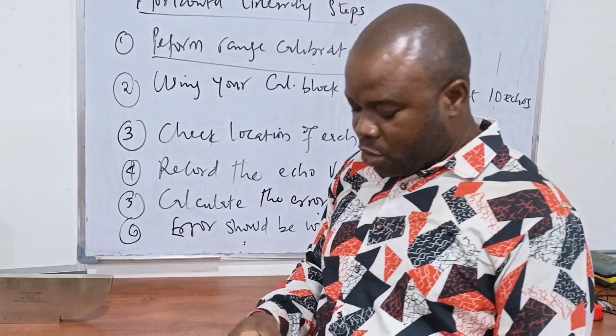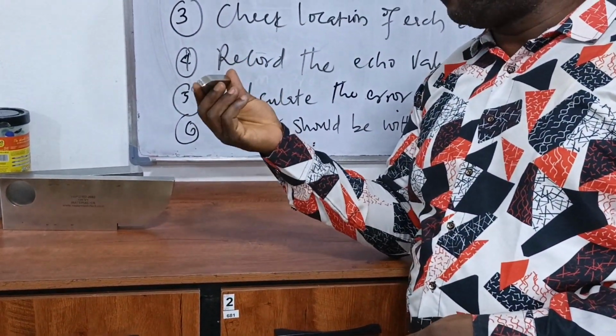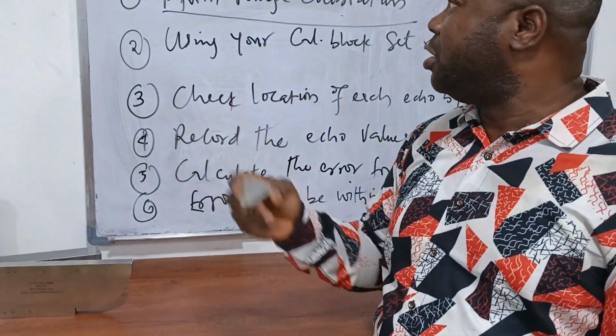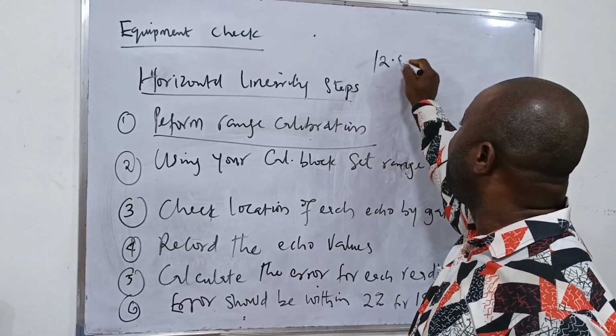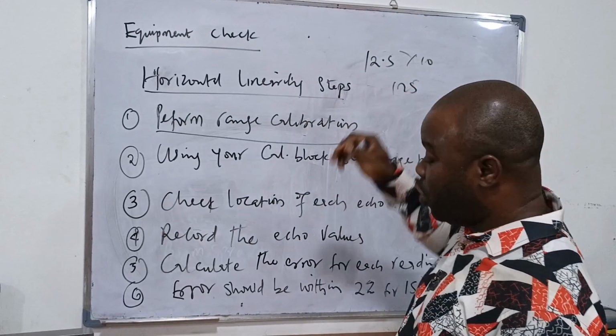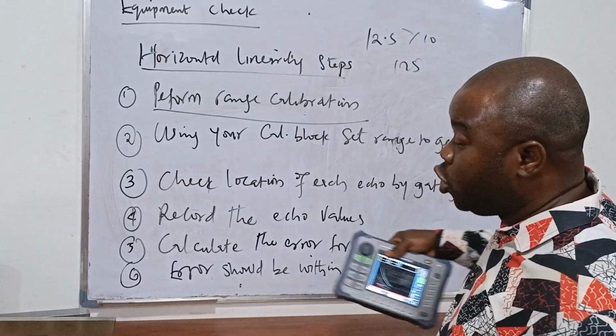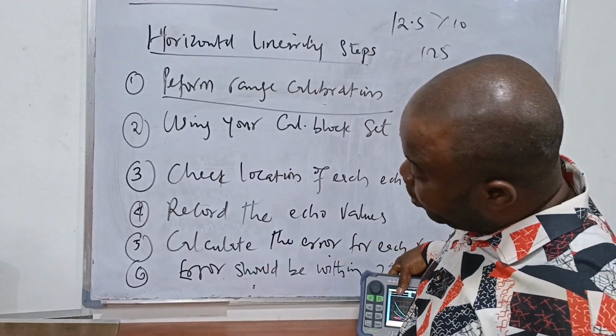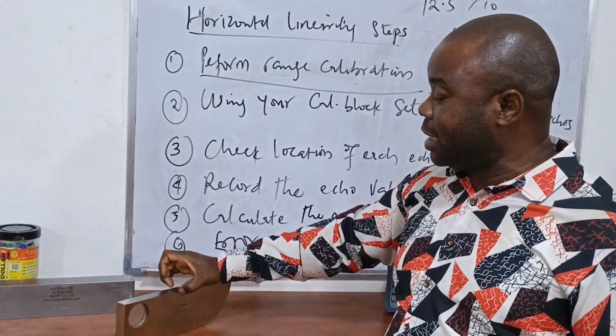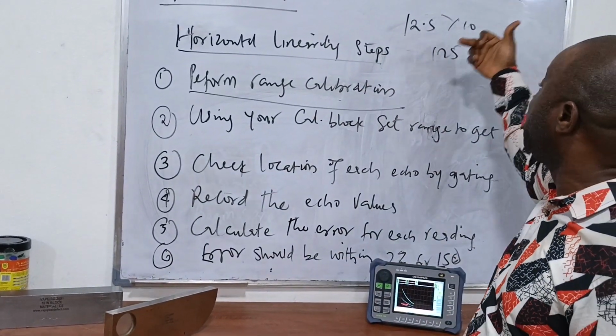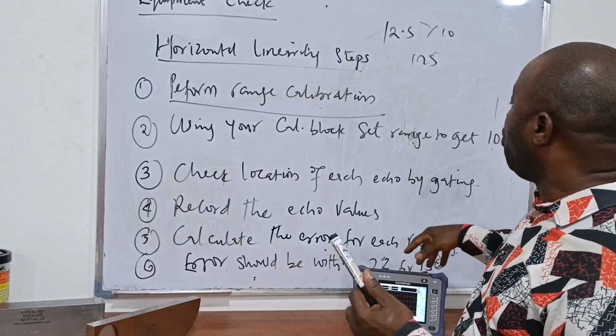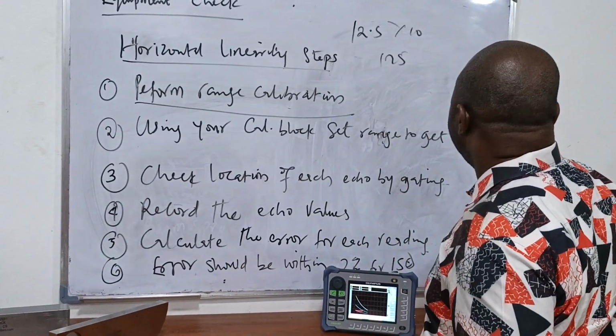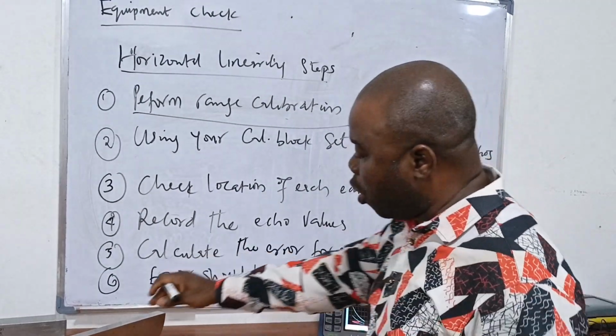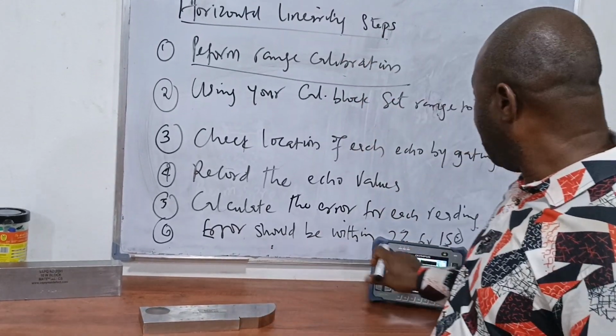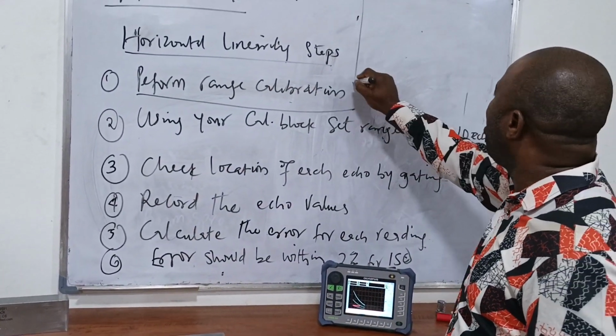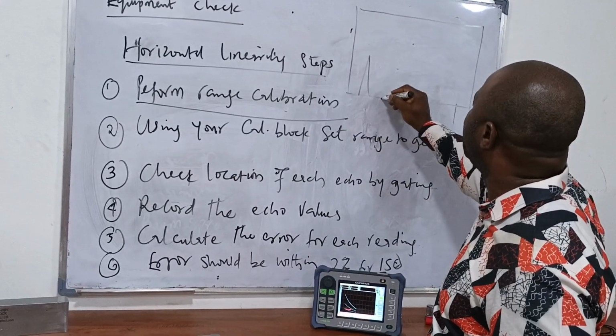What does that mean? This is a V2 block, 12.5 mm. If I want 10 echoes from this, it's 12.5 times 10, which is 125, which means I should set the range in my machine to be at least 125. If I'm using my V1 block that has a thickness of 25 mm, I should set my range to 25 times 10, which is 250. What does this do? By the time you put your probe on the block, with your range set, you are going to get 10 distinct echoes.